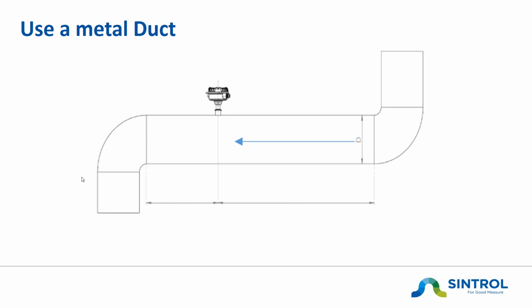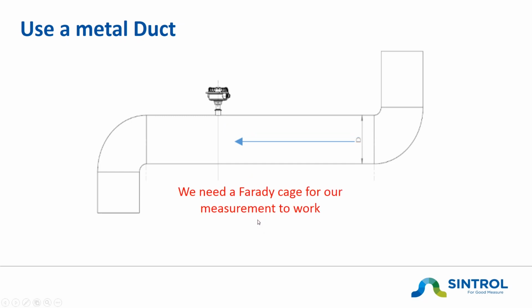Another important thing is that you use a metal duct to install our sensor. For our measurement, it's essential that we have a Faraday cage around our probe. So only a metal duct will give these conditions. If this is a plastic duct or something else, our measurement most likely will not work. In such cases, you could install a mesh wire, or for small ducts, you could even tape it with a metal tape. Just make sure that we have a Faraday cage all around our measurement place.